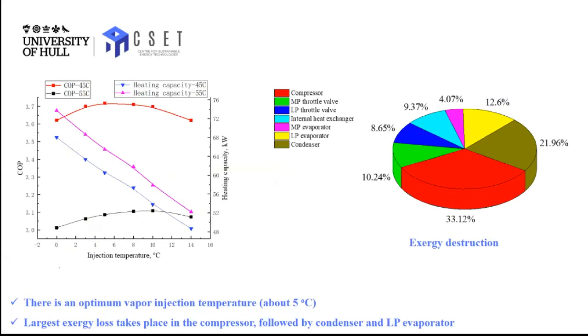Also, we look at the correlation between COP, heat output and injection temperature. We can see that at an injection temperature of 5 degrees Celsius the heat pump has maximal COP. There's an optimum. So in that case, we think the vapor injection temperature should be about 5 degrees, which is the optimal temperature. And we also analyze the exergy loss that takes place at different parts of the heat pump, including the compressor, evaporator, and condenser.